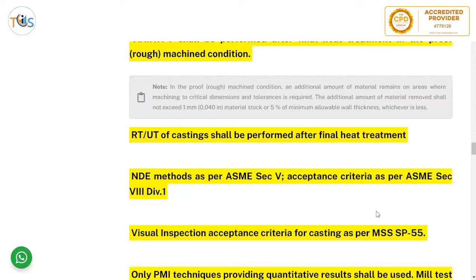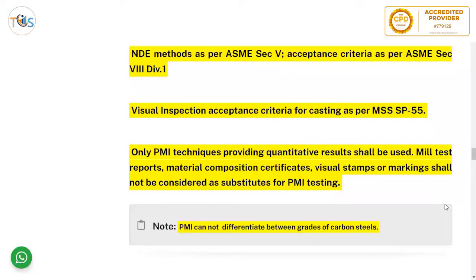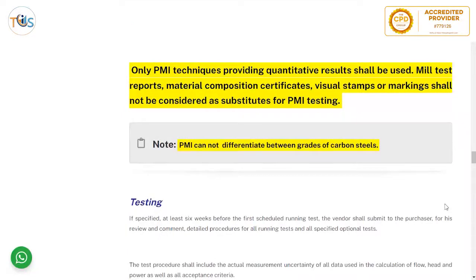NDE is done as per Section 5 and acceptance criteria as per Section 8 Division 1. Visual inspection acceptance criteria for castings is per MSS SP-55. Only PMI techniques that provide quantitative results shall be used, because some PMI techniques give only qualitative results — they identify what type of material it is without giving the percentage of alloying elements. Quantitative PMI shows not only the material type but also the alloying element composition.